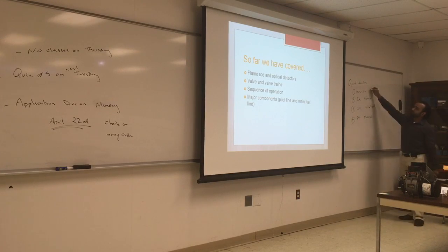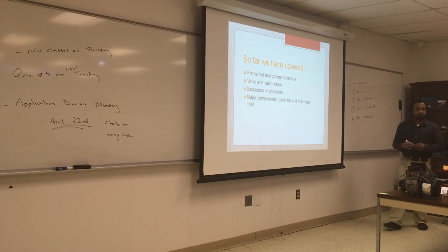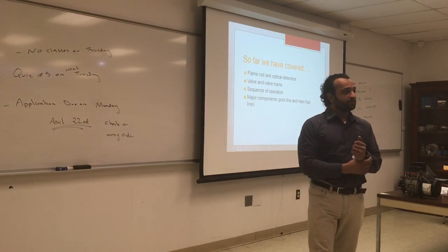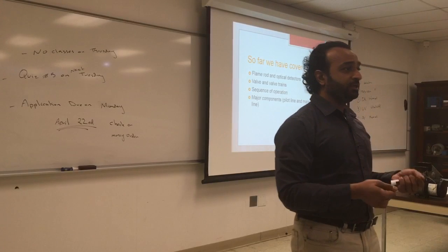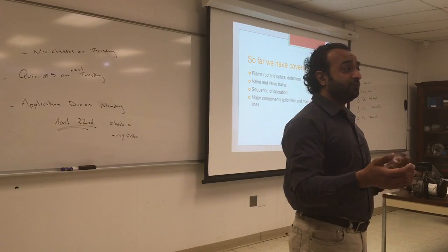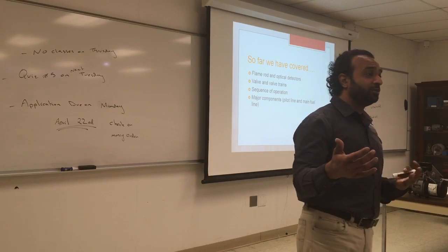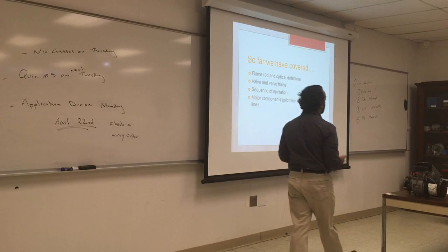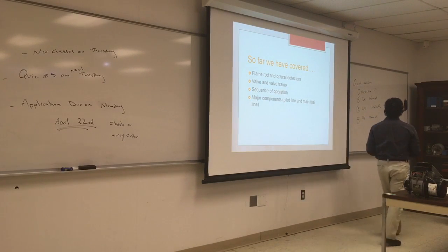So, do we use cad cell in industrial? No. It doesn't have the limits for the temperature and the amount of flame. And if you noticed, if you read the resistance for a cad cell when it sees a flame, it goes down to zero sometimes. So that doesn't give you a good scale. You want something that will gauge the amount of flame that you have. So cad cell is not that suitable for industrial.